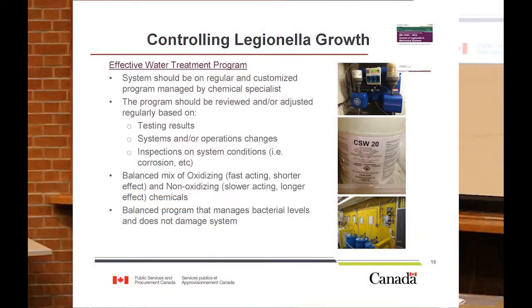So the ways that we can control Legionella growth, for the systems where we have a water treatment system installed, so cooling towers and open water systems, we want to make sure that it's a customized program to both the equipment on site and the materials of construction of the piping. What we don't want is somebody dumping in a lot of chlorine and causing a lot of corrosion in a system, because that leads to two things. One, it's going to decrease the service life of your equipment and you're going to have to replace it more frequently. But also it's going to add a lot of risk factors associated with Legionella growth.